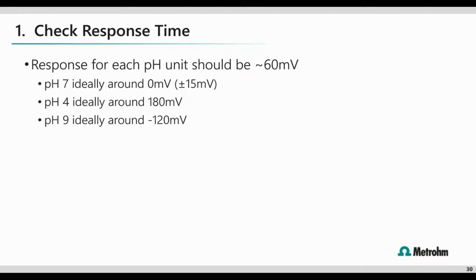Okay. Number 1, check response time. The response for each pH unit should be about 60 millivolts. If you start at pH 7, the millivolt reading for pH 7 should ideally be 0 millivolts, plus or minus 15, as Lori mentioned before. Each pH unit higher than 7 will decrease by about 60 millivolts, and each pH unit lower than 7 will increase by about 60 millivolts. So as you can see here, pH 4 is ideally around 180 millivolts, and pH 9 is ideally around negative 120 millivolts.